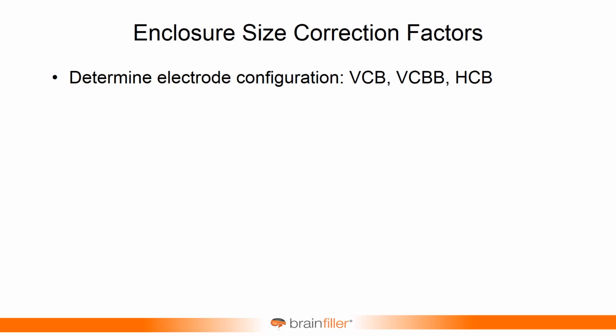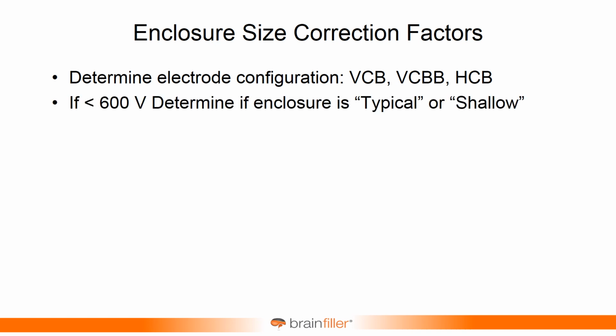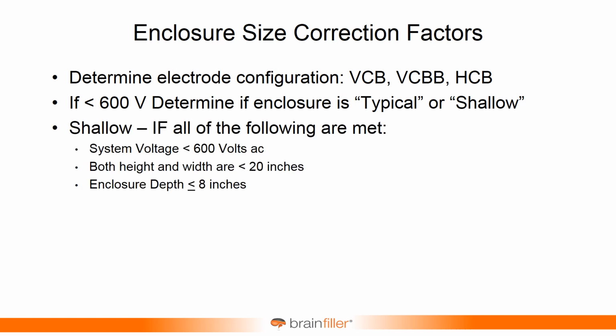And so to begin with, you have to determine, okay, it's an enclosure, so is it VCB, VCBB, or HCB? Those are the only 3 for enclosures. So you have to select which one of these you have. And up through 600 volts, you have the distinction between typical and shallow. And as I said, up through 600 volts, the height and the width can't exceed 20 inches. And then the depth, up through 8 inches, that's shallow, and then greater than 8 inches, that's going to be considered typical or normal.